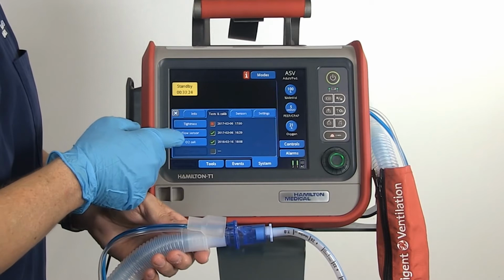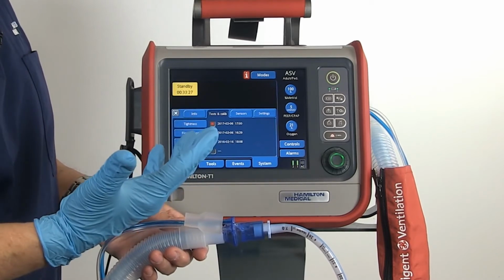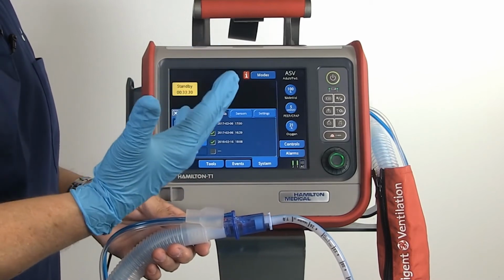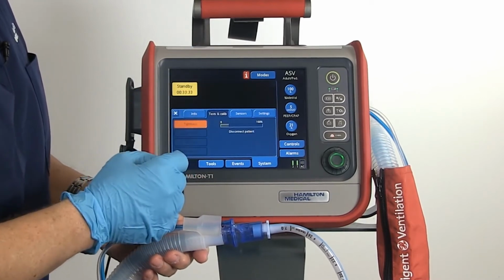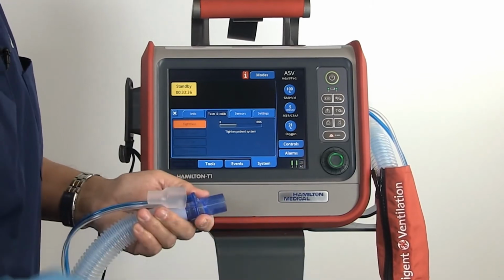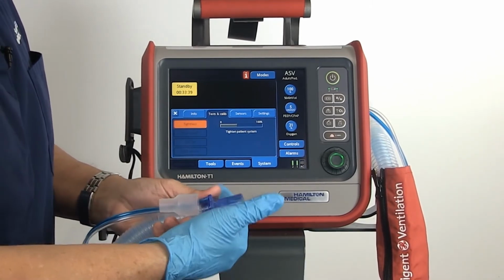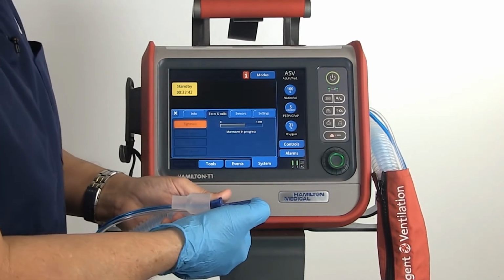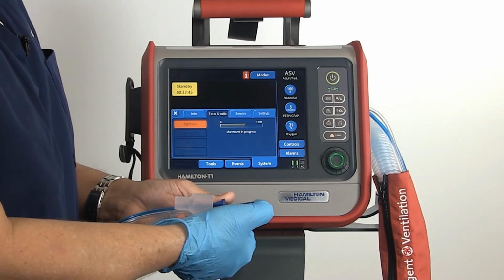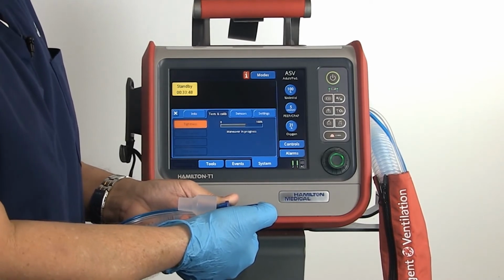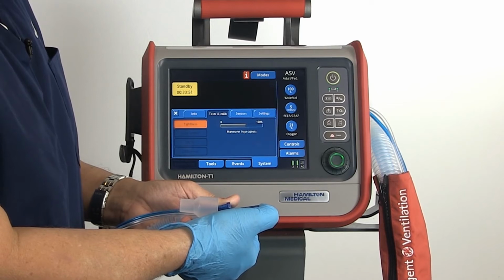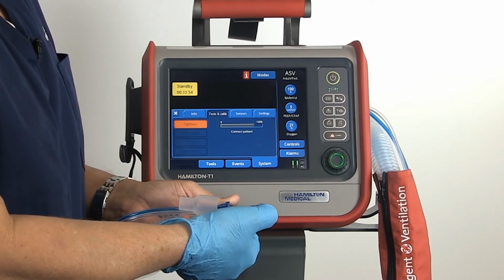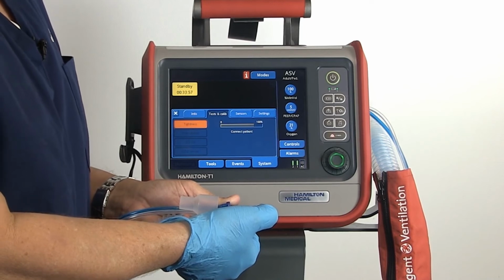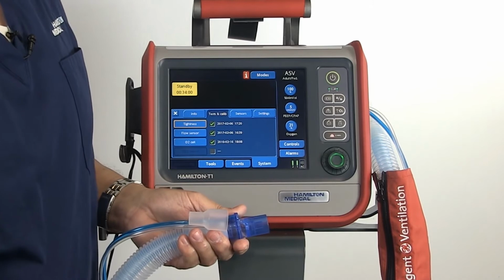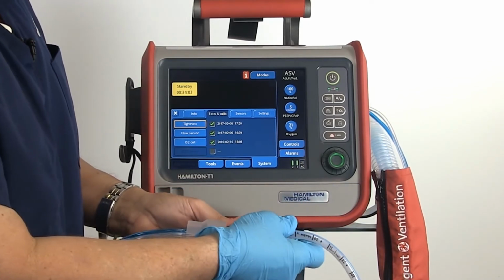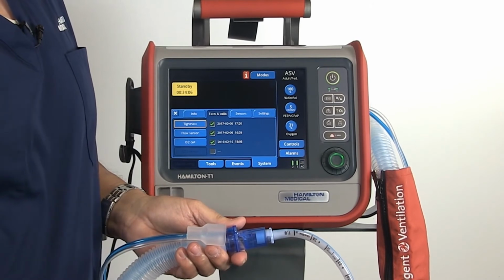So the first test we will run will be the tightness test. You always want to make sure, because you will be occluding the circuit, that you have a glove on your hand. Press tightness and you follow the commands. Tighten patient system. So at that point in time, with your gloved hand, you tighten the system or occlude the circuit. Follow the commands on the screen. As indicated, that was ramping up the pressure, and that was the safety valve. We passed the test as indicated by the green arrow.